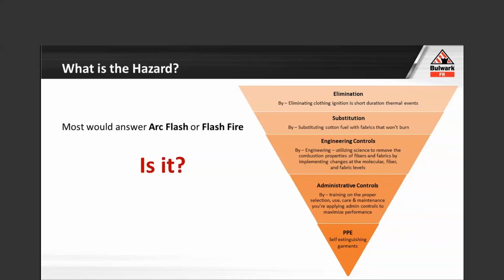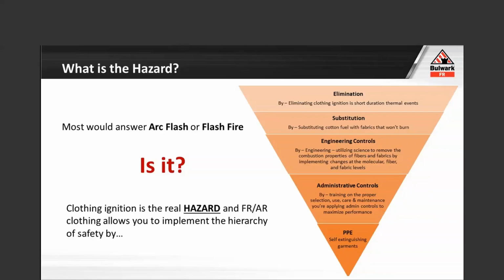So when we say, what is the hazard? Most folks would say arc flash and flash fire. Is it really? No. What we're looking to prevent, the real hazard, is clothing ignition—catching fire and continuing to burn—when we're up against these short duration thermal exposures like arc flash and flash fire.